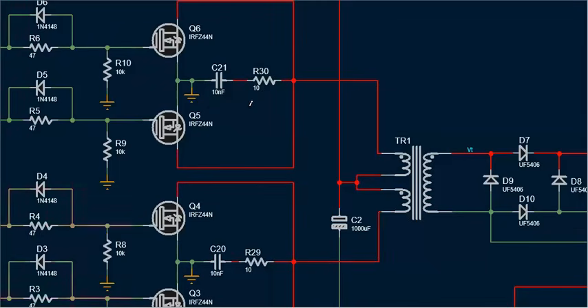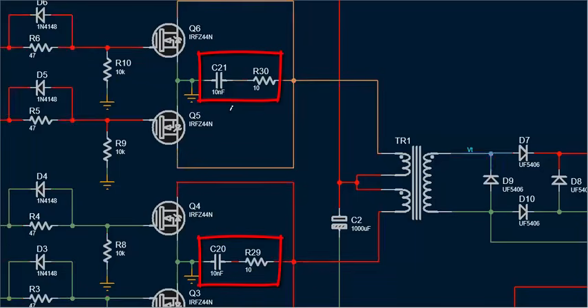Some points on R and C component selection: I've used a 10 nanofarad capacitor because it acts as a high-frequency bypass, capturing the energy of the spike. This should be a high-voltage ceramic or film capacitor, rated 100 volts or higher.